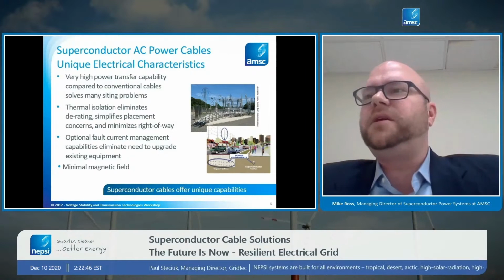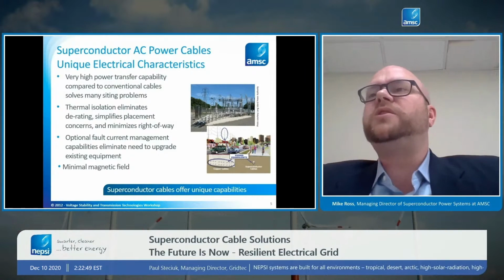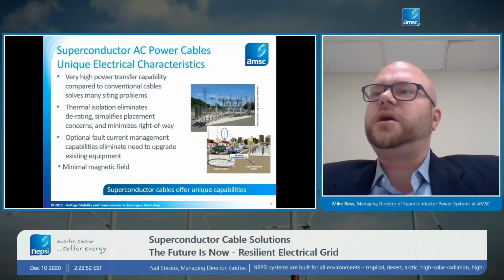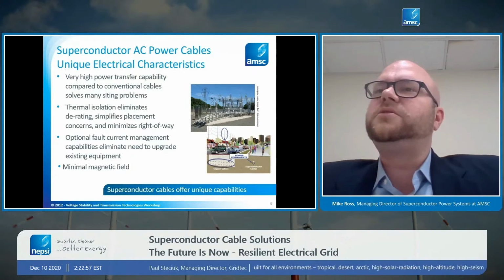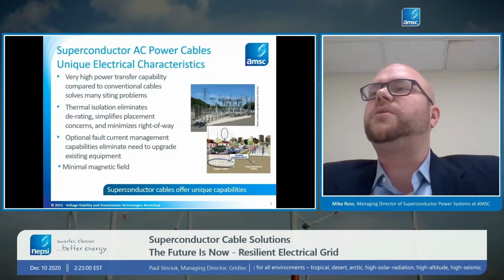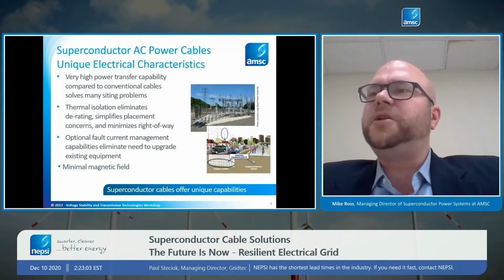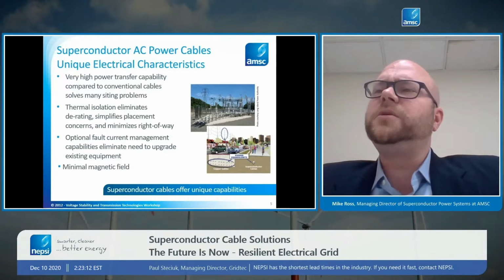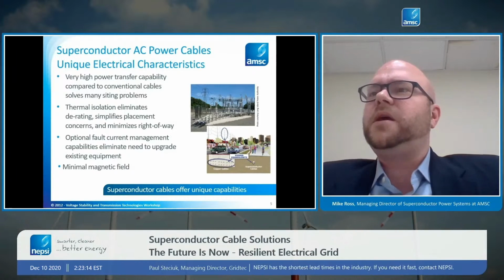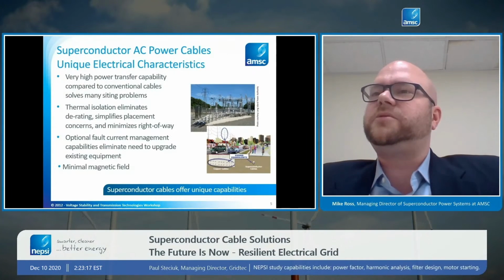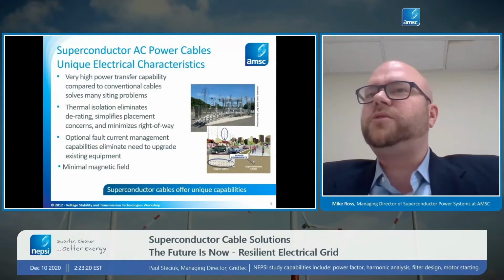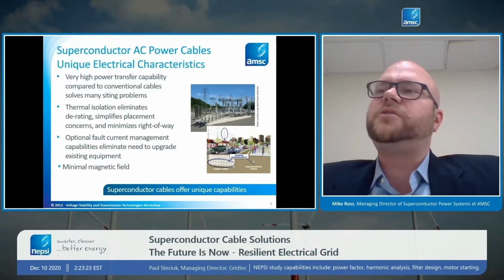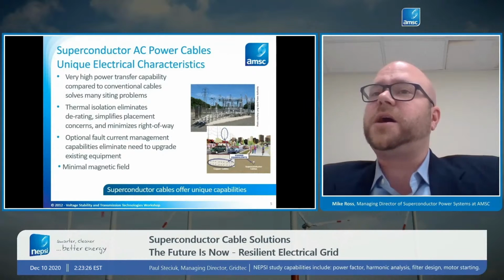And that is a very big deal when it comes to how to site these cables. We'll see soon that it gives the utility engineers options to make more direct cable runs. You can use installation techniques like directional drilling, where instead of ripping up the streets, installing a cable, interrupting traffic and having all the civil works required, you can simply horizontally directional drill and avoid those types of issues. So those are two incredibly important characteristics of these cables that differentiate them from copper cables.